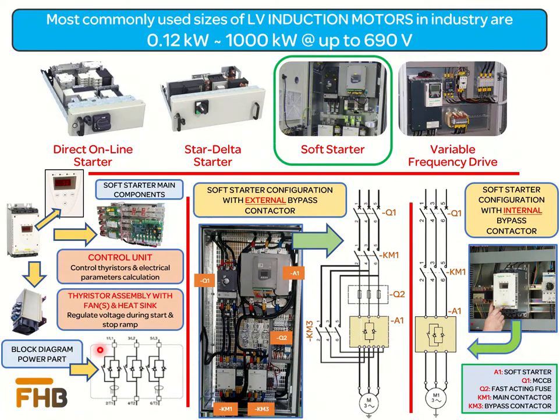Soft starter assembly consists of two basic components. The first is the control unit, which controls the firing of the thyristor based on voltage or current references. The control unit is also responsible for the calculation of different electrical parameters such as motor current, motor torque, active power, cosine phi, motor thermal state, and operating time.